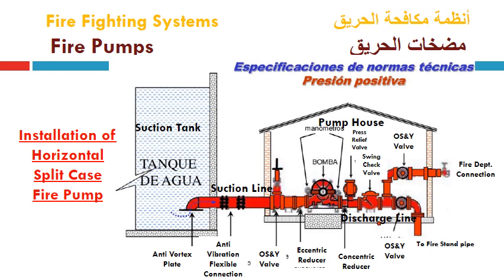This slide also continues how we can install a horizontal split case pump with a different configuration, but similar to the previous slide, we have the suction tank here and a suction elbow with an anti-vortex plate, and we can use an anti-vibration flexible connection here, one or two. Then we locate this isolation valve, an OS and Y gate valve, here vertically, and then spacing, and then we use the eccentric reducer to adapt the suction diameter to the suction flange diameter, and we use a pressure gauge on the suction flange. This is the pump with its drive fixed on a concrete base, separate from the fire pump room base.